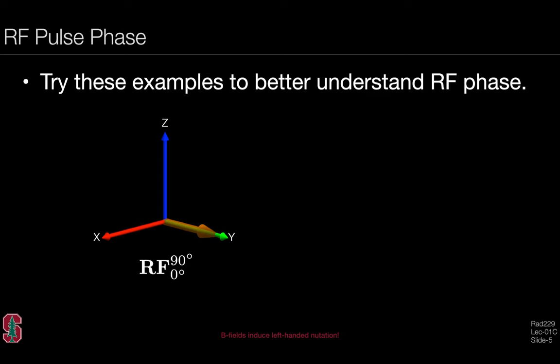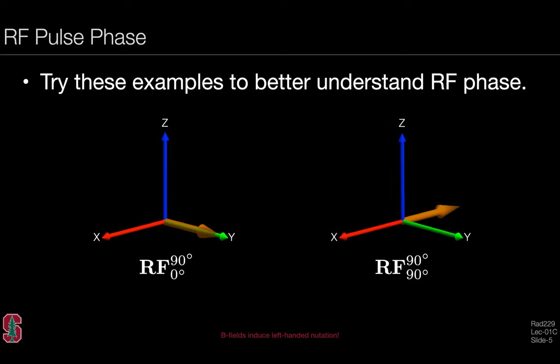We can try some examples to better understand the RF phase. In this case, the RF pulse has a phase of zero degrees and a flip angle of 90 degrees. If you align your thumb with the zero-degree axis, which is the x-axis, your fingers will curl the magnetization from its initial state along the z-axis down to the y-axis. Alternatively, if the phase is 90 degrees and the flip angle is 90 degrees, we rotate our thumb to point along the y-axis, and curling our fingers brings magnetization from z to the minus x-axis.